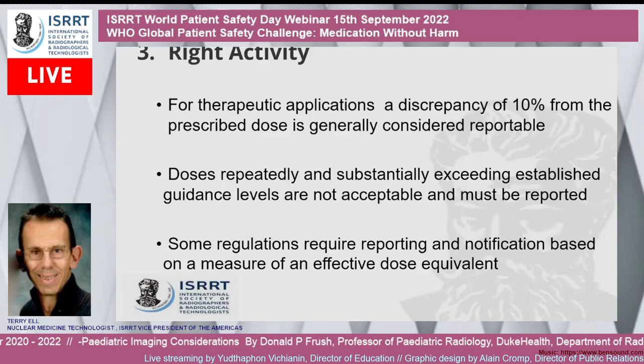A number of steps should be taken to ensure the correct activity is administered. We need to make sure that the dose calibrator is properly calibrated by always performing appropriate daily quality control procedures. It's not a bad idea to assess the calibration throughout the day as well. Check that the calibration factor is correct for the isotope being measured. On the right, you will see the significant effect the calibration factor has when assaying the sample.